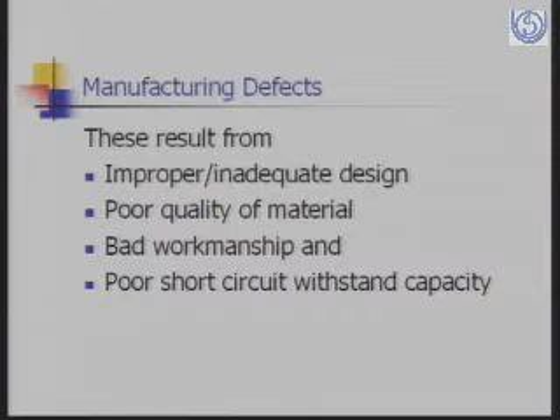And the percentage impedance should be large so as to increase their short circuit withstand capability. And this depends upon the size of wire used in the HV coil, and the radial distance between HV and LV coils. But usually, you know, the size is sometimes less and the radial distance is reduced, therefore the percentage impedance is reduced. Then there is improper use of aluminium wires, and aluminium wires are recommended only for ratings up to 200 kVA.